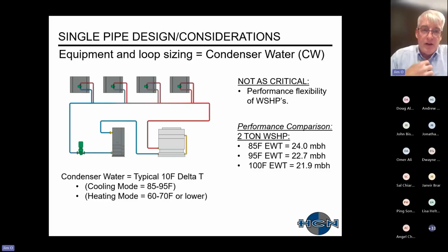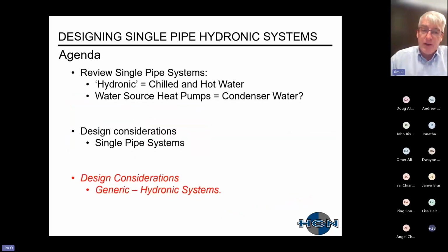And then in the worst case, the unit all the way on the right has an entering temperature of 95 degrees. You might think that's a big deal because it's 10 degrees. But really, because the water source heat pump essentially has a coaxial coil, it has very good heat transfer characteristics. So there really isn't any performance degradation or reduction with the warmer entering condenser water temperatures on a water source heat pump system. And once again, try to follow the max number of units on a loop, et cetera.